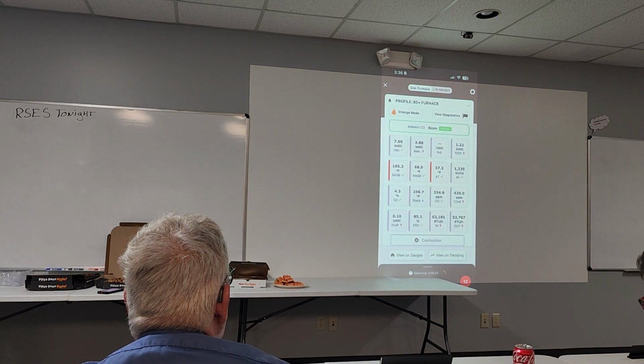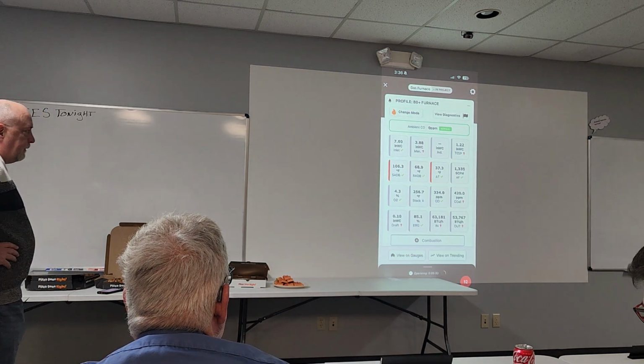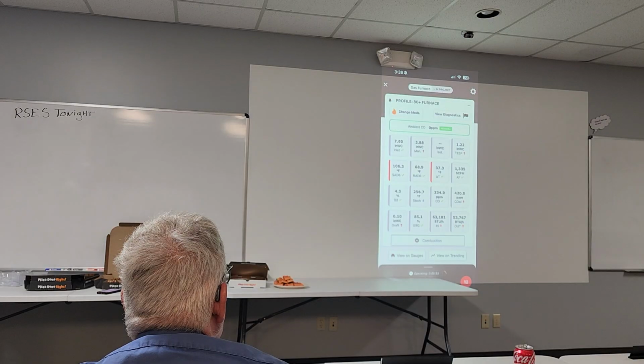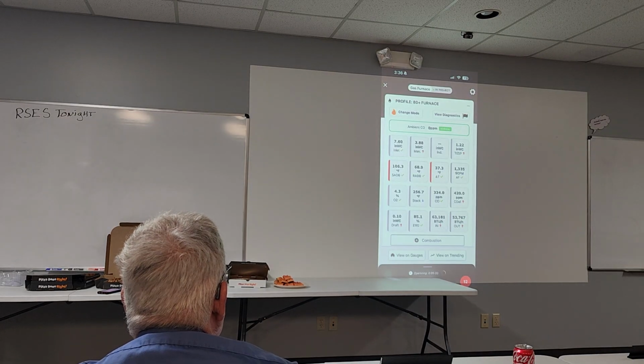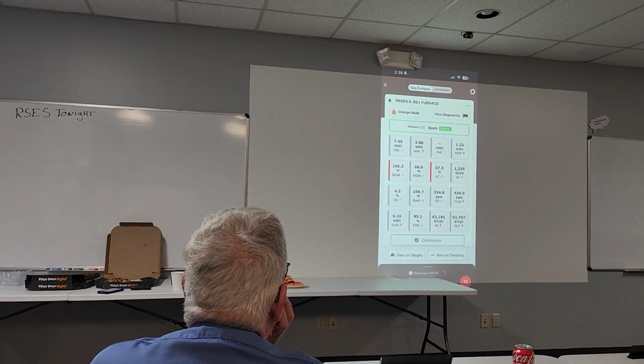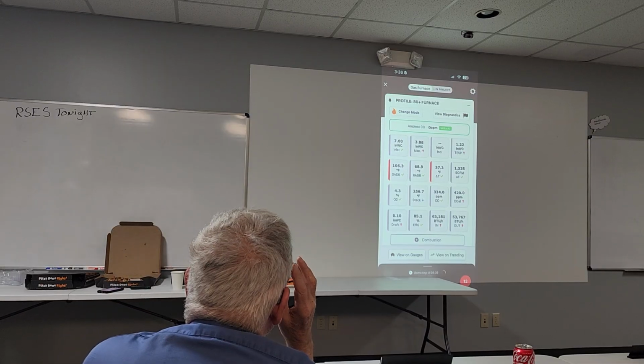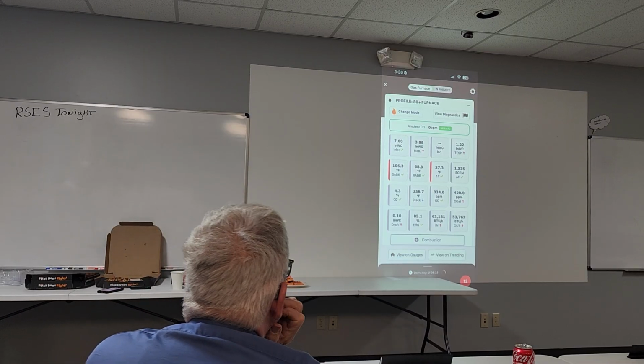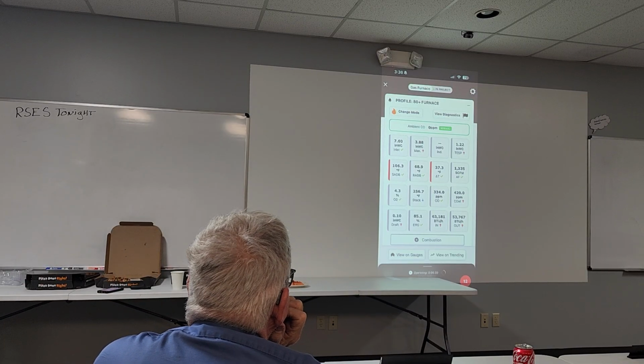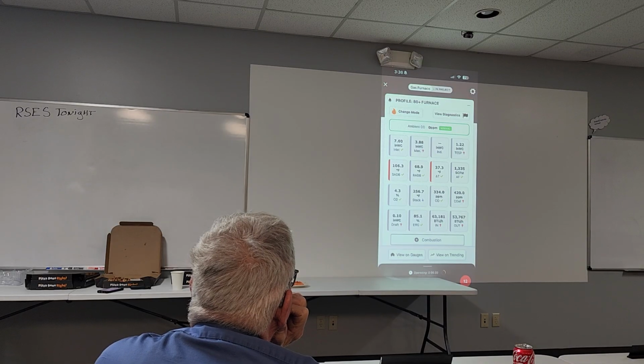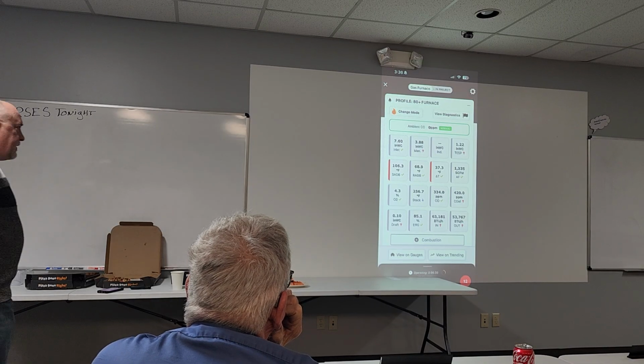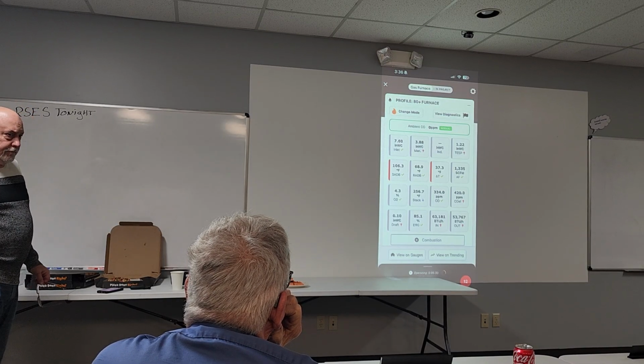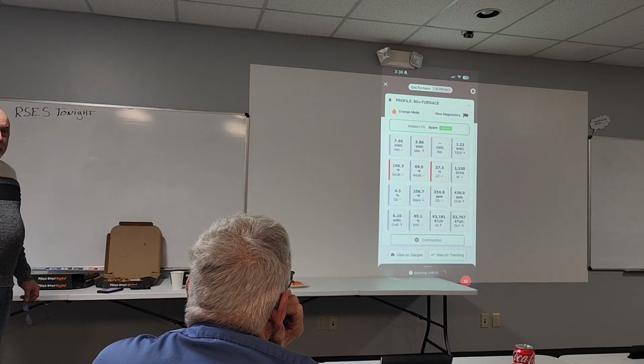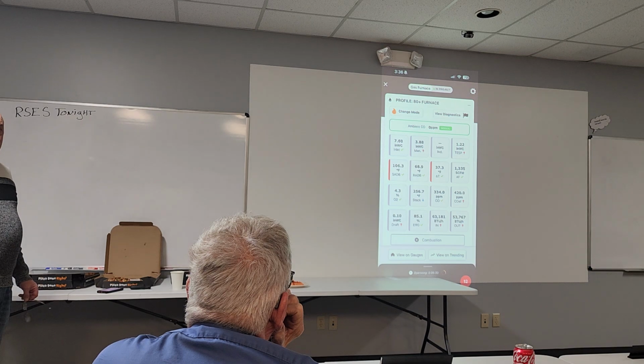This is a gas furnace, obviously. It's an 80% efficient, 60,000 BTU input is what it's rated at. And there's a couple things there. CO air free, what does that number tell us right there? It's not safe to leave it there. We're over 400 parts per million CO air free.